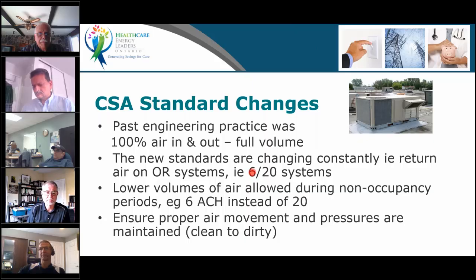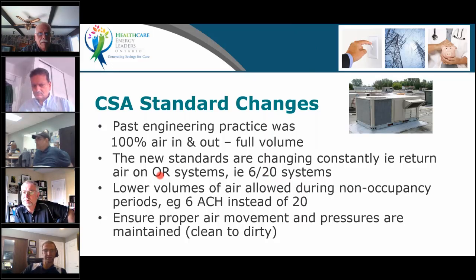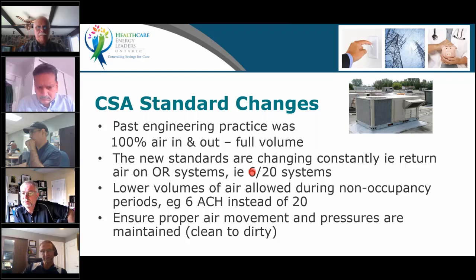620, I would mean 6 fresh air changes per hour over a total of 620 recirculated airflow. So, operating rooms used to be sometimes 100% fresh air, let's say a 15-15 system or a 10-10 system. Nowadays, with the latest standard, you can have operating rooms that are 620. That means they recirculate a good portion of the air. Obviously, they have high filtration requirements, but they are not 100% fresh air.